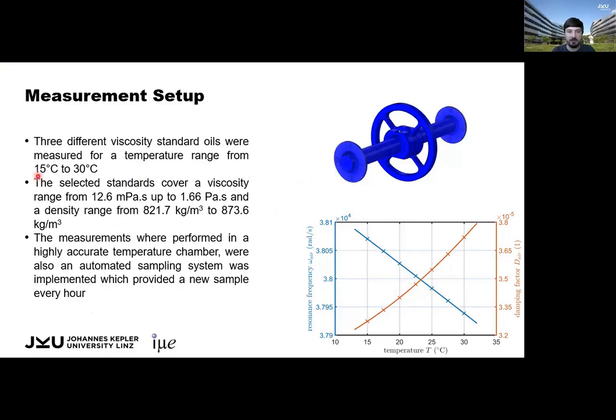The temperature range was from 15 degrees Celsius to 30 degrees Celsius, and the viscosity range was from 12 millipascal seconds up to 1.6 pascal seconds. We also measured the air-loaded resonance characteristics of the sensor to calculate back to the unloaded resonance characteristics.